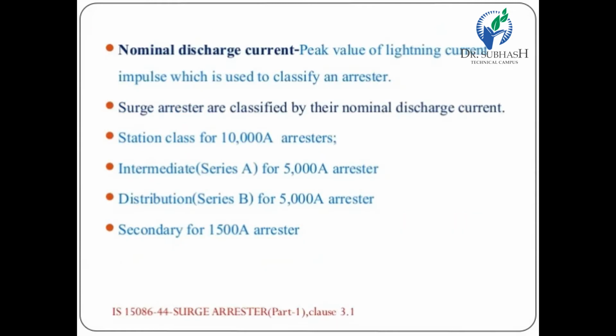Nominal discharge current. The peak value of the lightning current impulse which is used to classify an arrestor is known as the nominal discharge current. Surge arrestors are classified by their nominal discharge current.